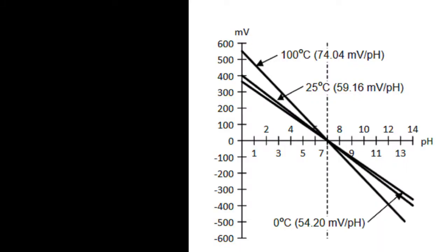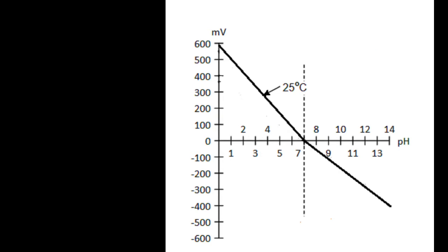The net effect of the probe in this case is generating a very small output voltage, on the order of around 60 millivolts per pH as far as the slope. And yes, that output voltage is definitely temperature dependent. As you can see here, the higher the temperature, the greater the voltage slope. On a good high quality pH probe, that output is linear with respect to pH. Here we come to the first problem with my inexpensive probe. It's not linear. Chances are this actually curves. It's not actually two straight lines. Now, if I was controlling a process with this probe, I'd definitely be concerned. But in this case, all I'm trying to do is get a pretty good value of about what the soil pH is, so I'm not too concerned about the variation here.